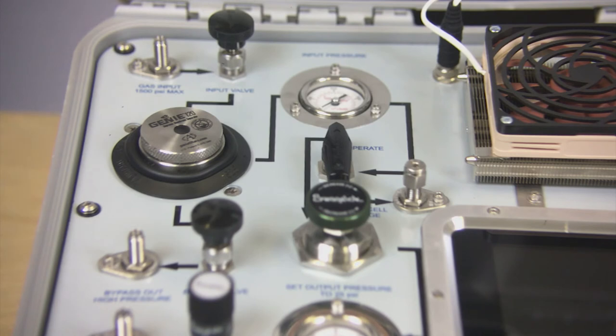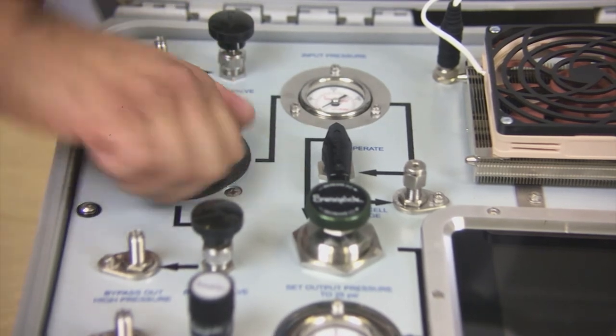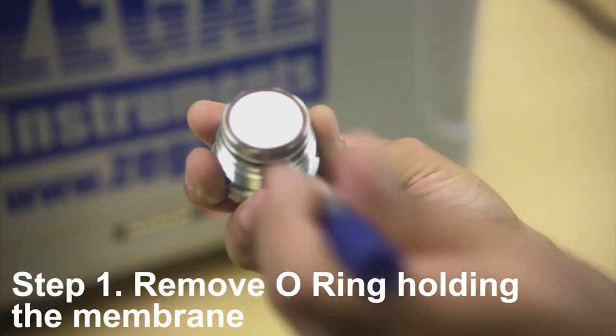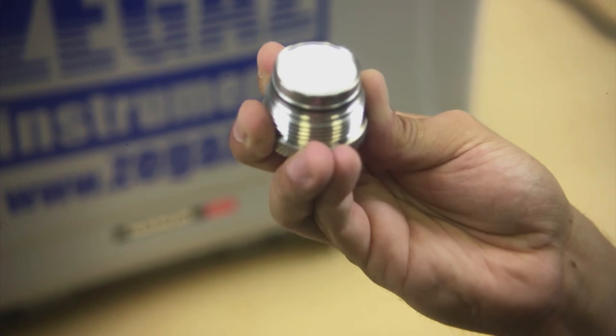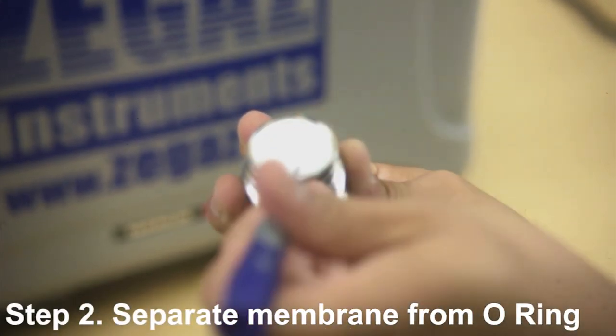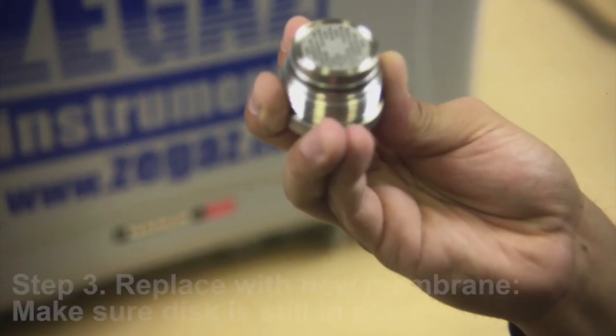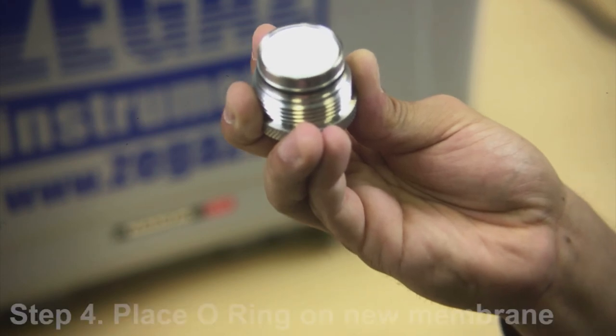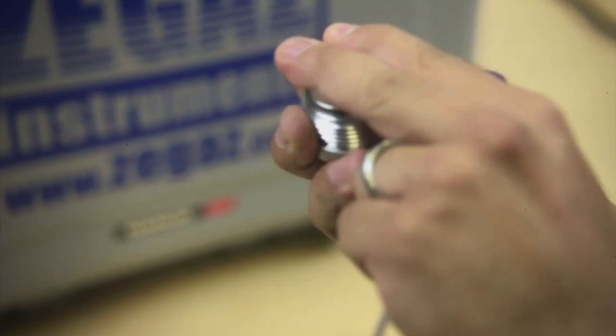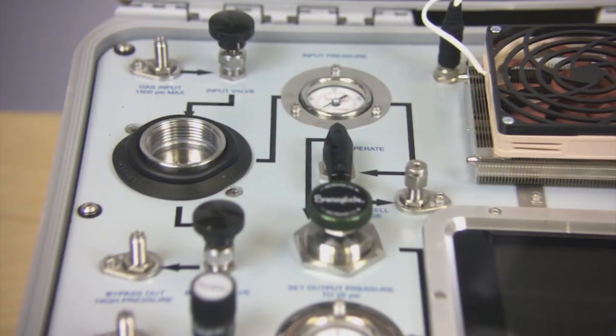To change the membrane filter, make sure that the system is powered down and all gas connections have been removed. Confirm depressurization by opening the bypass valve and viewing the gauges. Unscrew the filter head. Remove the O-ring holding the membrane. Separate the membrane from the O-ring. Replace with a new membrane. Make sure the disc is still in place. Place the O-ring on the new membrane to secure in place. Screw the filter head back into the housing.